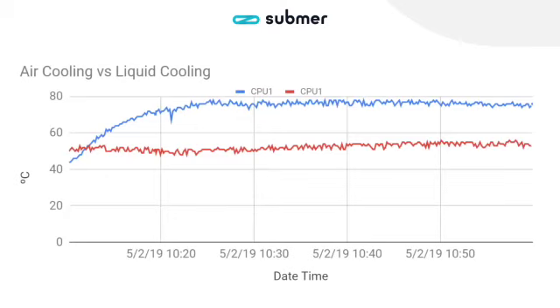I wanted to share some of the tests we've been doing in air and in liquid. I've taken one particular CPU core to keep it simple. We have a set point in the bath, in the tank, of 50 degrees centigrade for the liquid cooling. For the air, we're talking about a standard data center environment with an ambient temperature of 20 degrees, fed by CRAC units, and yes, we're talking about a densely packed scenario.